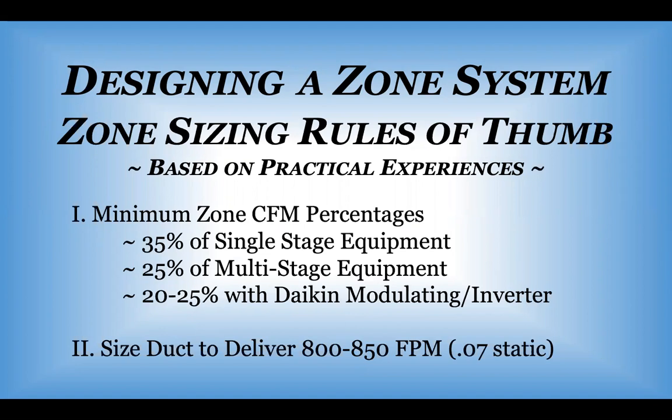Single stage equipment requires that no zone be less than 35% of the total CFM. Multi-stage, no less than 25% of the total CFM. And modulating inverter, 20 to 25% of the total CFM. What does that mean? On a 1,000 CFM system, 2.5 ton, 350 CFM is the smallest a zone can be with single stage, 250 with multi-stage, and 200 to 250 with modulating inverter.